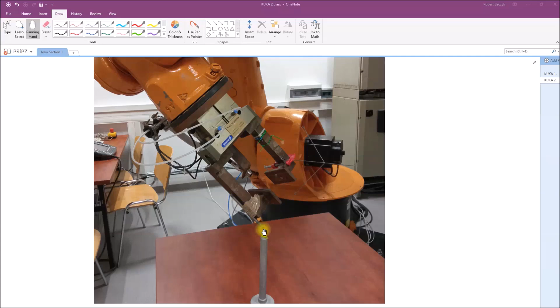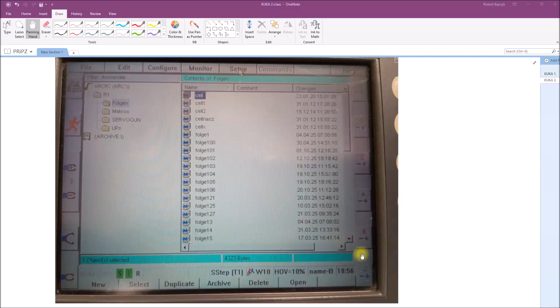we should keep the pen close to the reference point, switch to the global reference frame, press the deadman switch, and now you have access to 3 angles of rotation. Try to rotate the tool and observe if the end of the pen stays at the same place, continuously close to the reference point. If it is okay, it means that the tool is correctly calibrated. So this was the subject of the first class, and now we continue the calibration process.